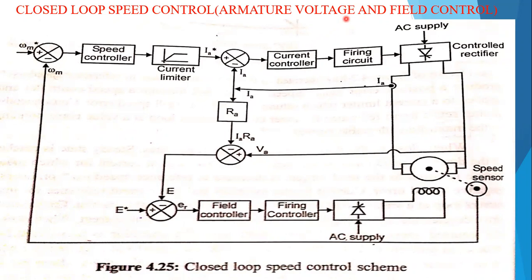You know well the field control mechanism formula: N is equal to EB by phi. The flux is inversely proportional to the speed. Flux weakening control means above base speed. If the field current is decreasing, the flux decreases and the speed increases. The field can be controlled only within limits, so that the poles of the DC machine do not saturate.